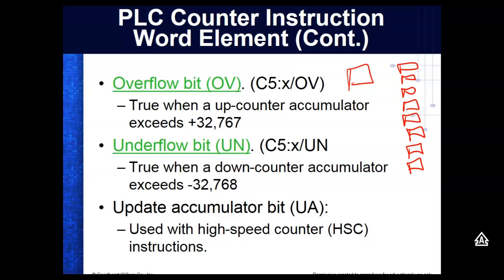So they've literally put high-speed counters back in. So what you do is you read the accumulator every once in a while. The counter never misses a count, but you'd go out there and read it every second or so. Your count would update. But those suckers don't miss a count. So we have high-speed counters. I don't remember how many are in this one. I think it's got like 3 or 4. But that's available to you. And it's on one of these inputs, so it'll tell you which input you would use for your high-speed counter. So every PLC that we've had for quite a while supports these high-speed counters.